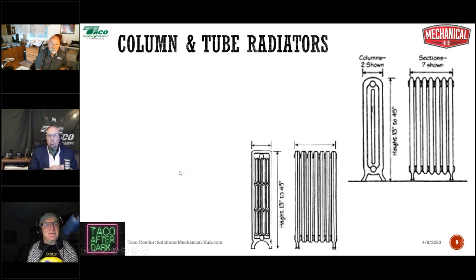I do want to talk to you about sizing column and tube radiators, because in a lot of older areas, you go in and there's no baseboard to measure, all right? You have to look at what the output possibility of the radiators is. Maybe you do a heat loss, but how do I know what the output of these cast iron radiators is, and how do I work with that?